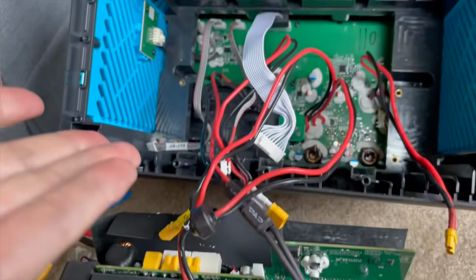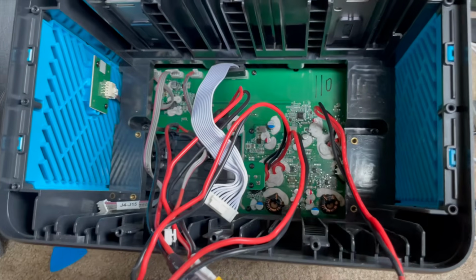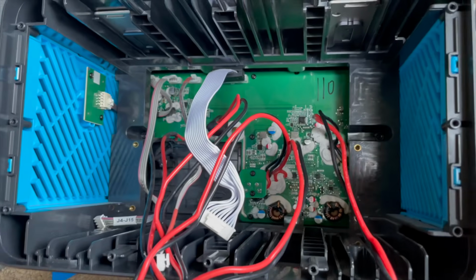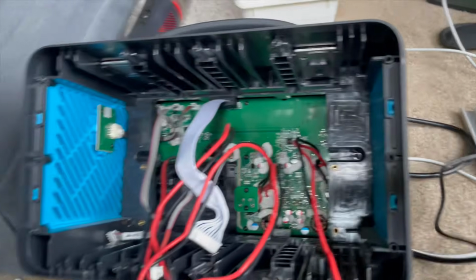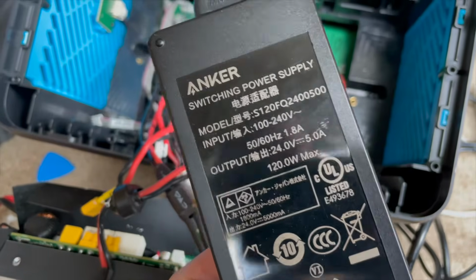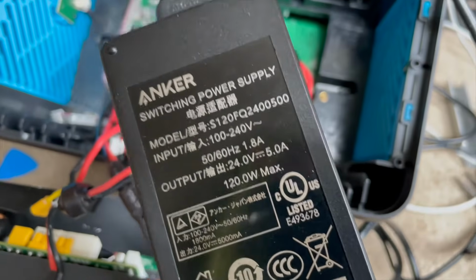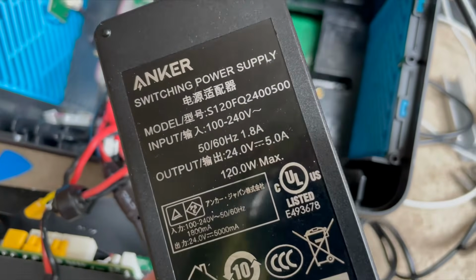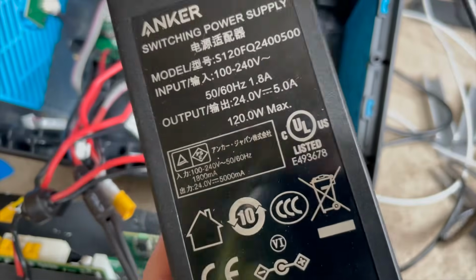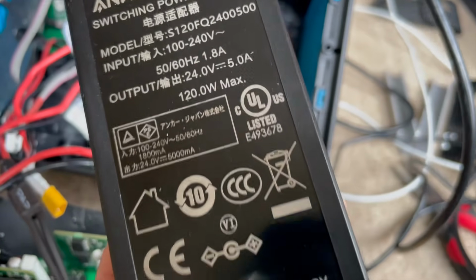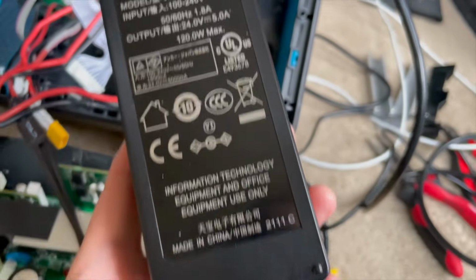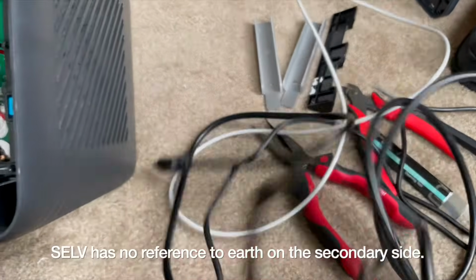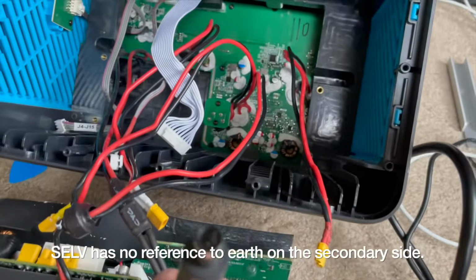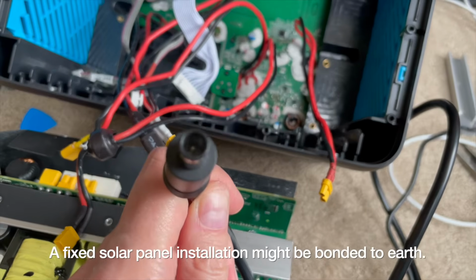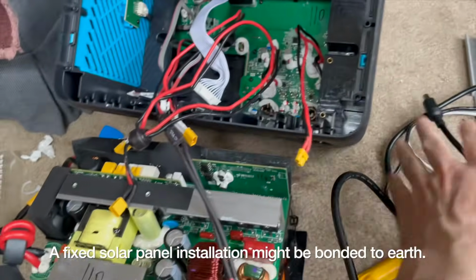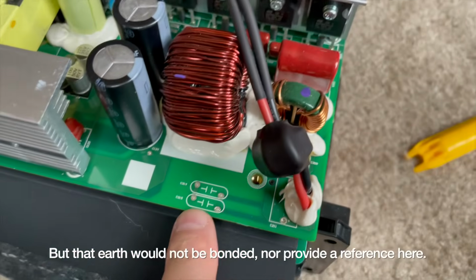Not even when it's plugged into mains AC - there's no external grounding because it's all on an isolated supply. This is the main supply here. If you're charging it with this brick, the Anderson plug, a solar panel, or a car socket, all of which are safety extra low voltage supplies, an SELV supply has no ground. There's no earth ground on this, it's just DC positive and negative, that's it. So it's an interesting construction, and I can see perhaps why they decided to omit this.